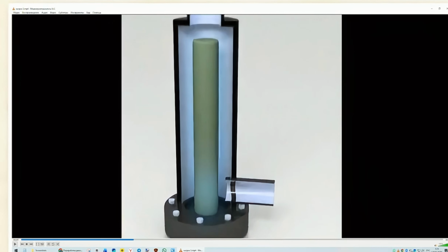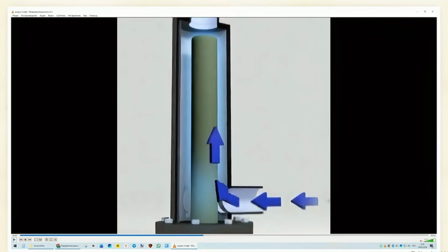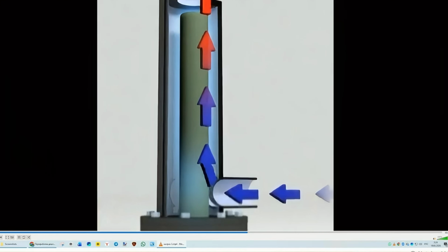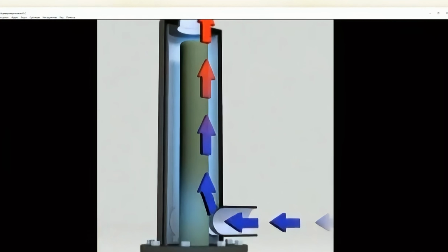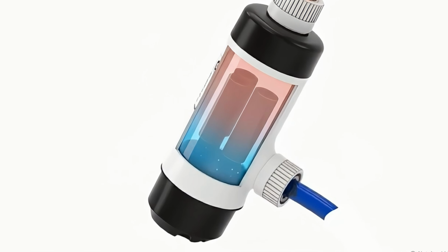Let's watch the complete operational cycle, starting from a cold, dormant state. Cold tap water is introduced into the lower inlet of the casing, quickly filling the empty void surrounding the central electrode rod. The moment the water bridges the gap, the circuit closes. Current passes through the fluid, the ions oscillate, and the water immediately begins generating thermal energy as it is pushed upward through the chamber. A continuous, uniform temperature shift takes hold inside the casing.